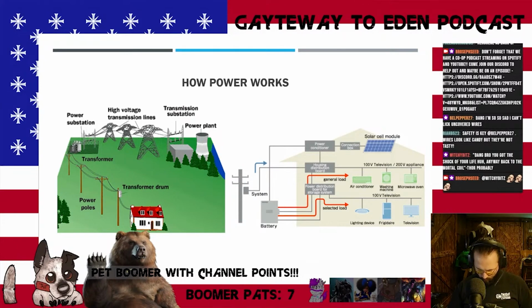You have your solar cell module connected via a connection box to the power conditioner, and then the housing distribution board typically feeds your 100 volt and 200 volt appliances. Then you have a power distribution board for the storage system, which is your battery, that has a selected load of basically 100 volt appliances that, according to this, exists on a separate circuit.